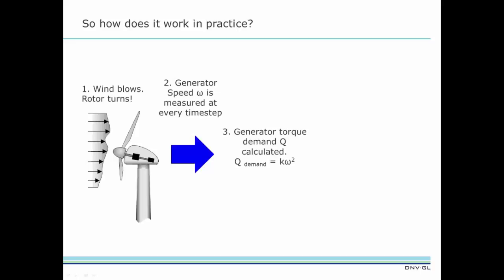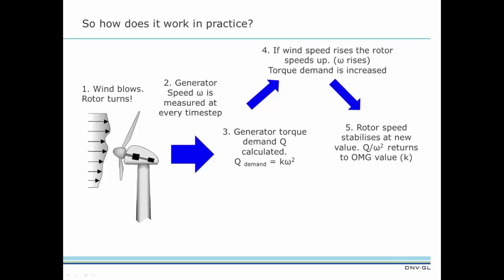If the wind speed rises, the rotor speeds up. This means the torque demand value will also increase. The effect of this increased torque demand is to stabilize the rotor speed at a new, slightly higher value.